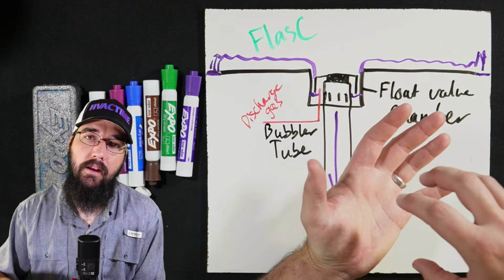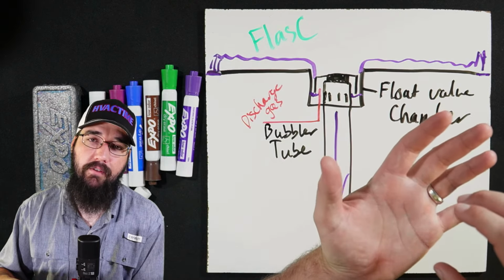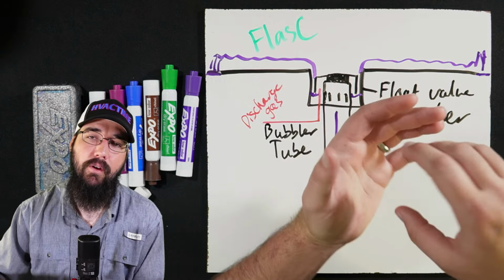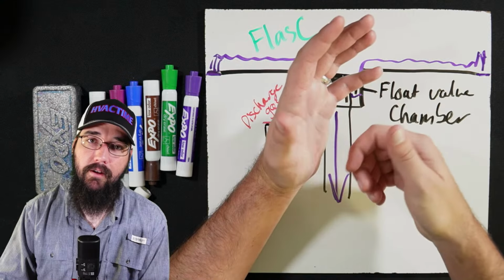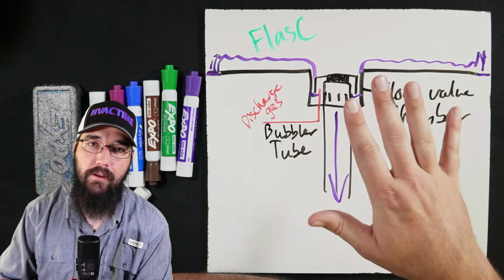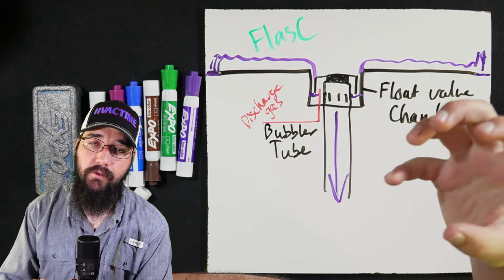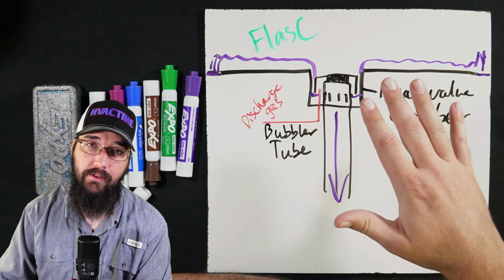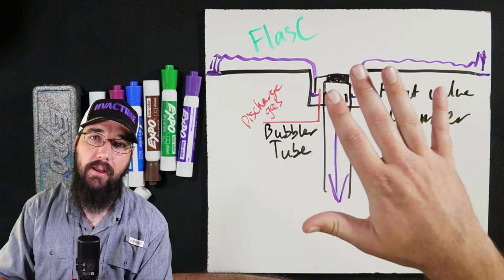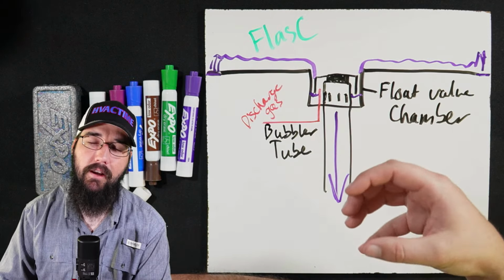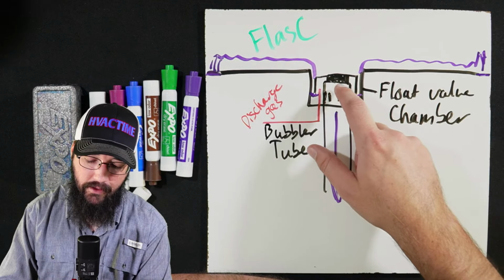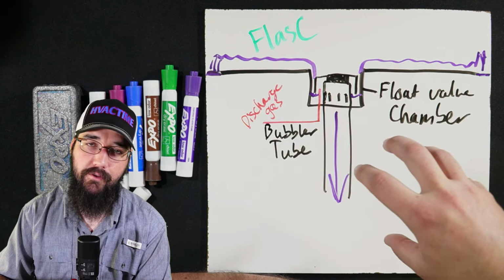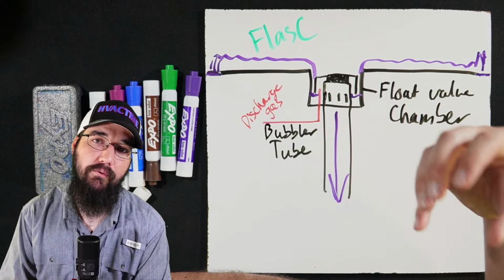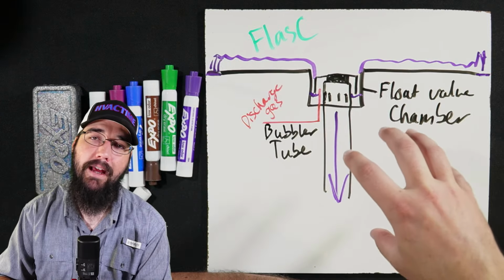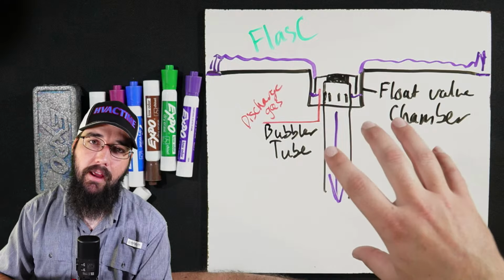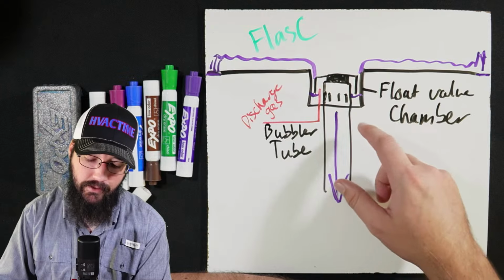When you take a cup and you have a bowl of water, and you put the cup upside down into that bowl and make an air seal, then you can push that cup underneath the water level. Water doesn't necessarily go into the cup. The air creates an airlock and holds it, but the cup has buoyancy, right? That buoyancy makes the cup want to push back up out of the water because it has air trapped inside. That is the exact same principle this type of bowl is using with floating on that liquid refrigerant. Because this bowl is full of vapor refrigerant, it's going to have a lighter buoyancy than the liquid refrigerant does, and that allows it to float up and down on that liquid level as it's modulating through.